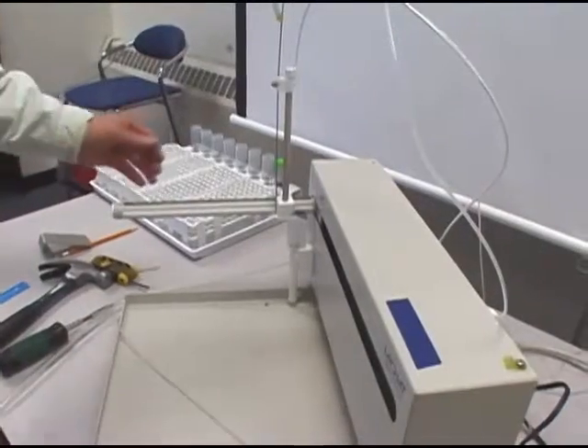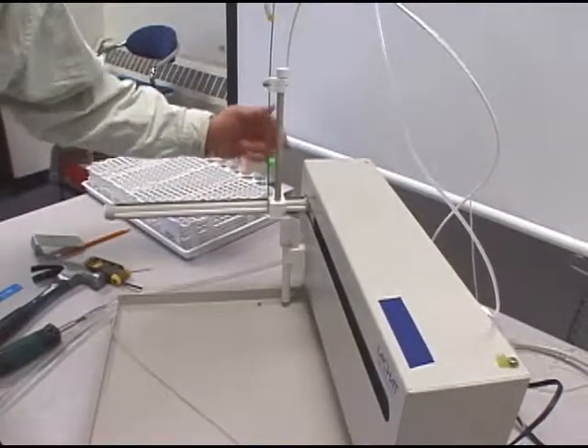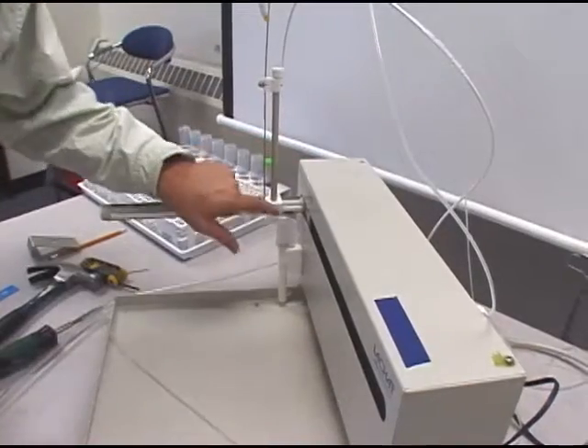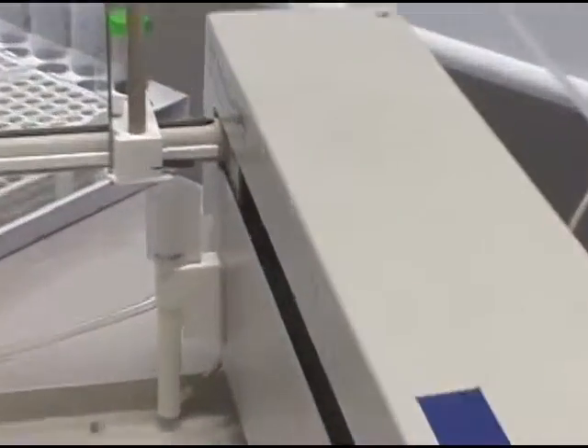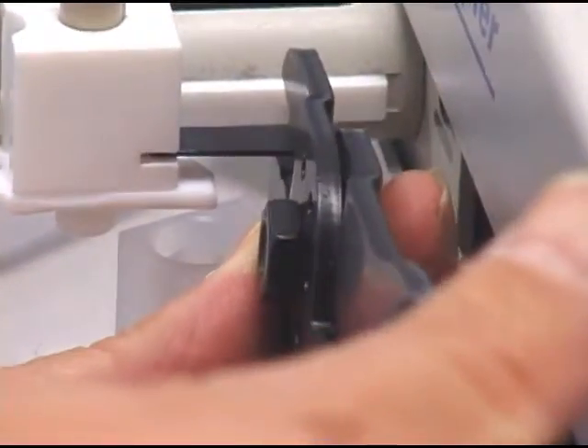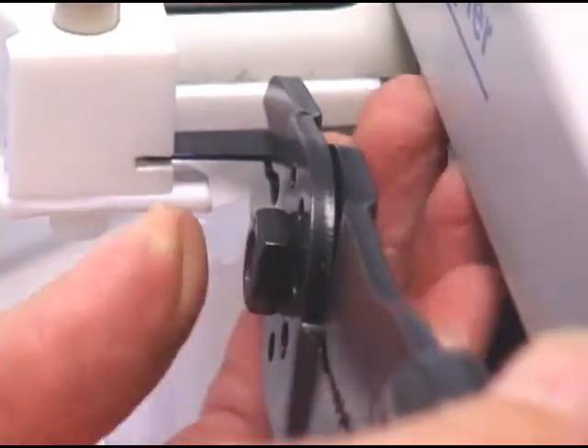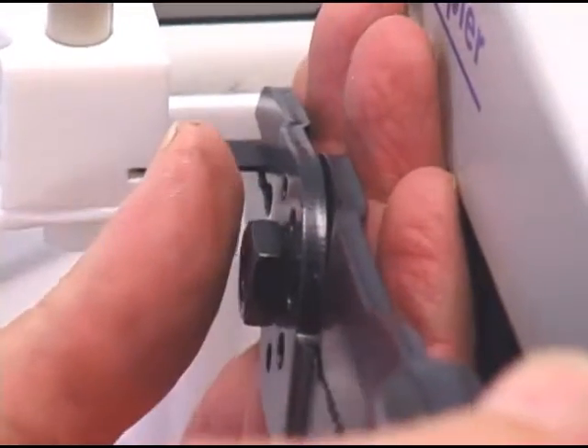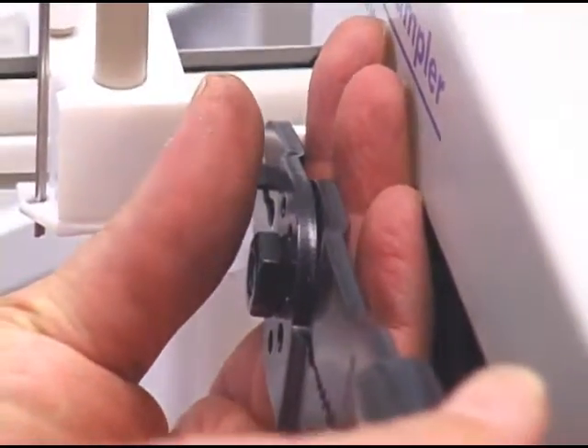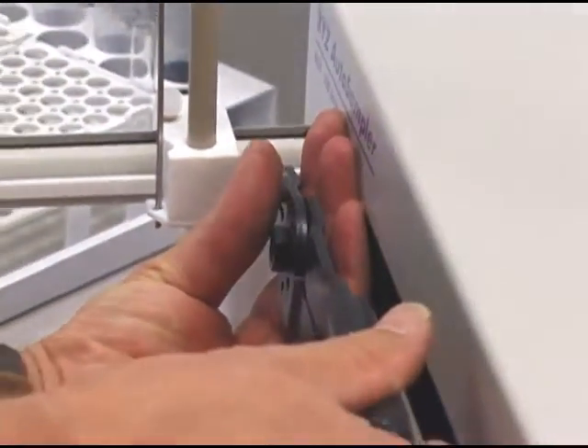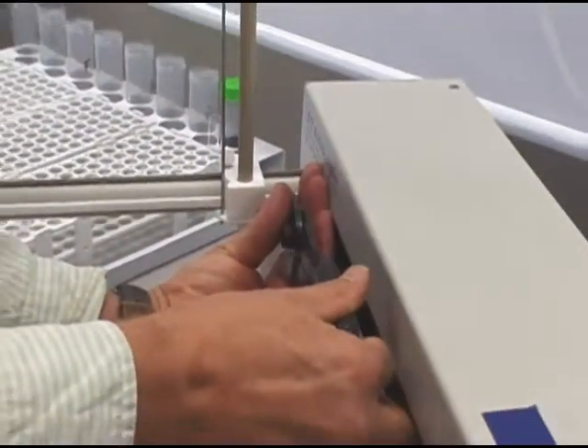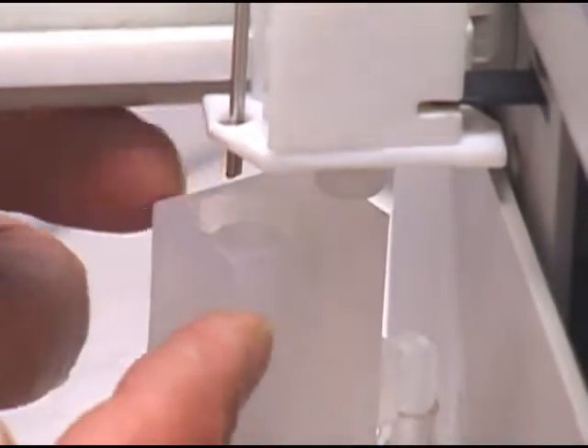Okay, if the probe is too far forward and we need to push it back a little, what we have to do is take that flag and cut it back a little bit. So you take a pair of cutters and trim off that flag a little bit at a time. Make sure when you trim it that the piece that comes off of that flag does not go into the mechanisms of the auto sampler. If the probe is too far back, what you have to do is extend that flag.